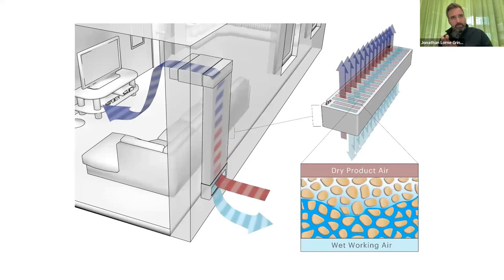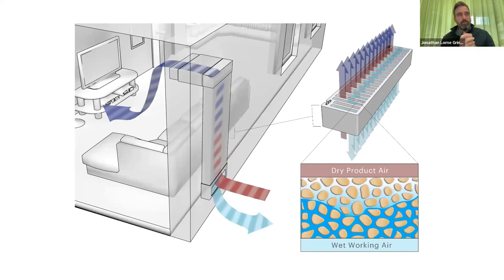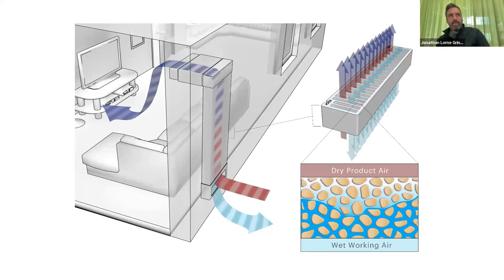And so we've envisioned the first iteration of this as a retrofit wall system where we can bring in direct air from the outside. We can improve ventilation. We create a ceramic heat exchange module using this barrier layer. And so the air comes in warm. It's cooled in the dry channels. Some of it then gets redirected into the wet channels where we have the evaporation and cooling. And so ultimately we have what's called a sub-wet bulb cooling system where we can cool the air down below what a typical direct evaporative cooler would do without, again, adding that extra moisture.